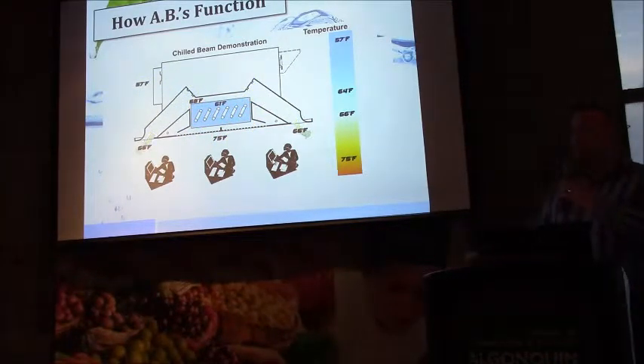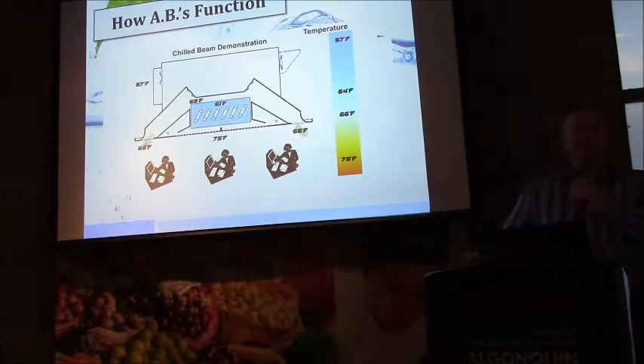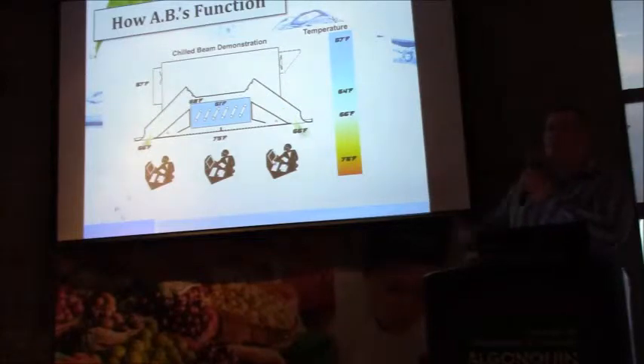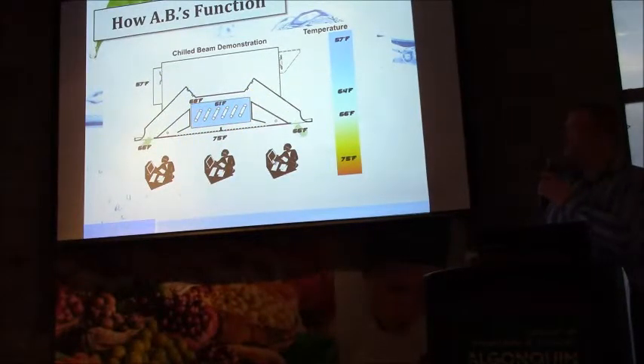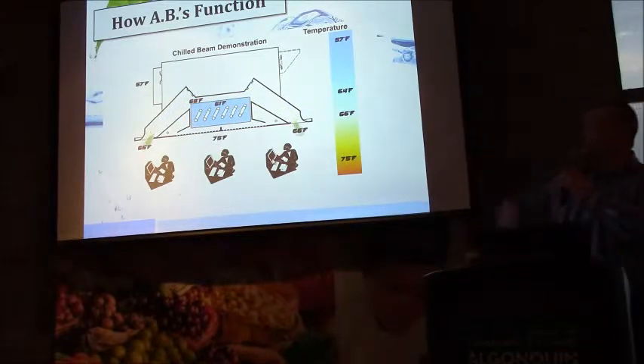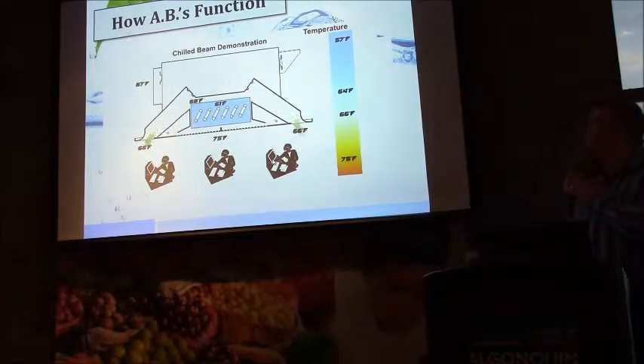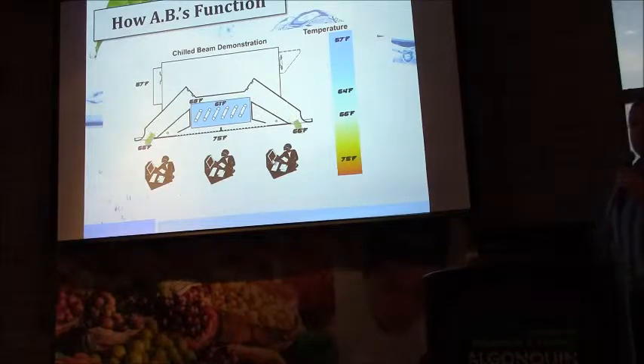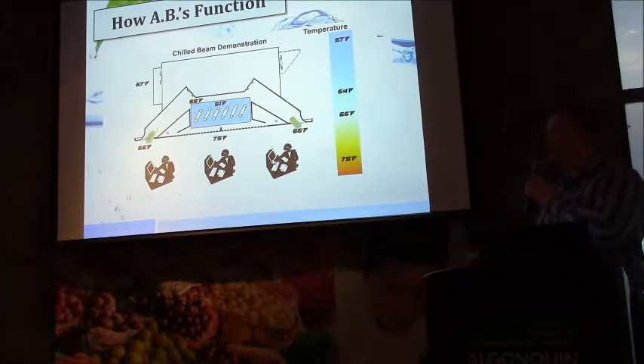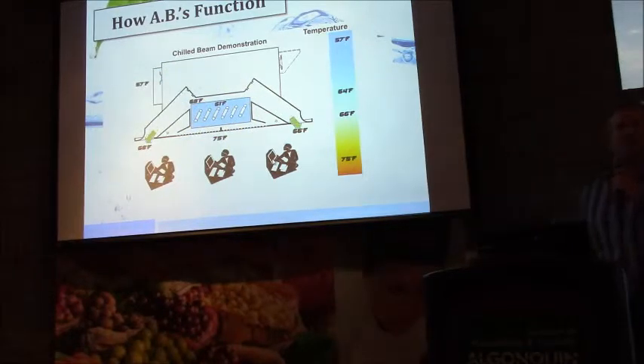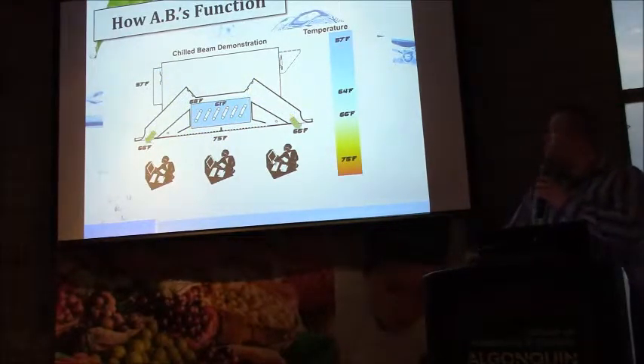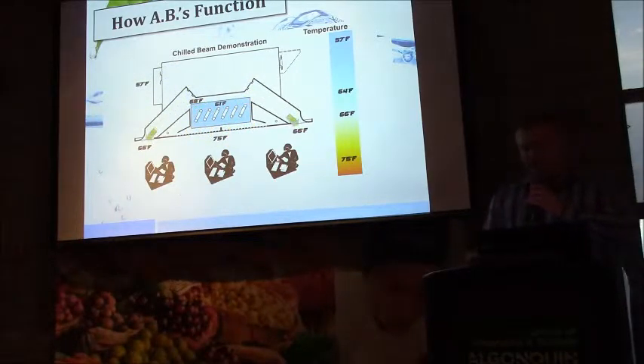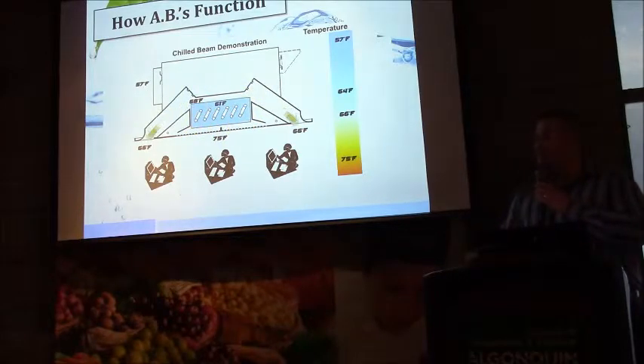The primary air supply temperature is not so critical in terms of its dry bulb temperature because of the mixing that happens within the chamber. But in this case, it's 57 degrees. The room air rises through natural convection into the coil, which draws the heat from the space and is delivered to the space at temperatures that are roughly half of what you would expect to see in an all-air solution in a straight-off coil condition. That might look something like 55 degrees Fahrenheit. Again, here we see that the coil is held above the dew point to ensure that we don't condense, and that's one of the primal rules, I guess, of active beams in terms of how they're applied.